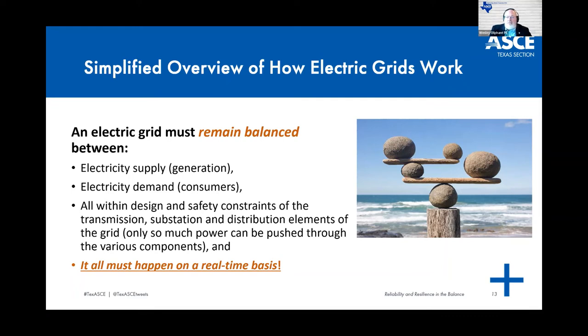That's changing. But when there is an increasing demand for electricity, when all the ACs kick in as temperatures rise during the day, or electric heating strips kick in as temperatures fall during the night, the supply of electricity must be immediately turned on to match that increasing demand. The operating frequency, as I mentioned earlier, is 60 hertz or 60 cycles per second. And if that begins to vary, when supply and demand are not balanced in real time, we run into real problems. In simple terms, if there's too much demand for electricity, again, we turn our heaters on or our ACs on, and we end up with an increase in demand, and we do not have enough electricity being generated and fed into the wires to meet that demand, the frequency on those lines drops.